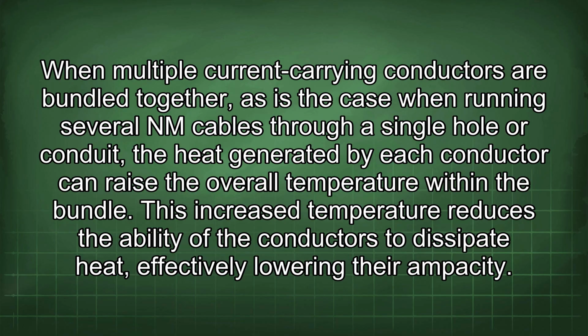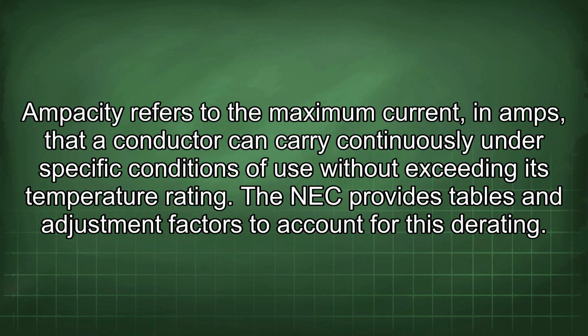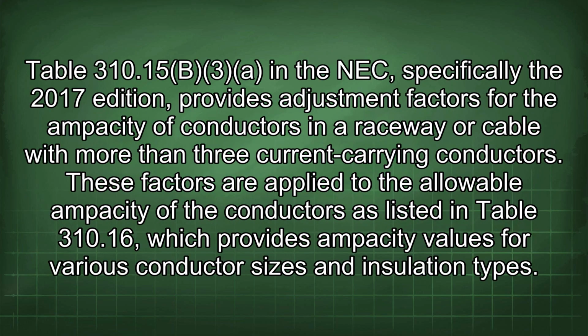This increased temperature reduces the ability of the conductors to dissipate heat, effectively lowering their ampacity. Ampacity refers to the maximum current, in amps, that a conductor can carry continuously under specific conditions of use without exceeding its temperature rating. The NEC provides tables and adjustment factors to account for this derating. Table 310.15(B)(3) in the NEC, specifically the 2017 edition, provides adjustment factors for the ampacity of conductors in a raceway or cable with more than 3 current-carrying conductors.